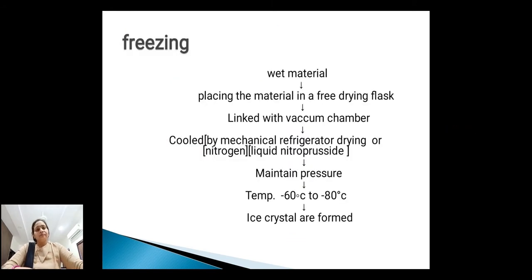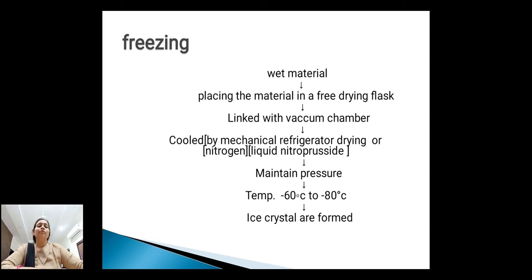Freezing. In this process, first we take wet materials and place the material in a freeze drying flask. After that it is linked with a vacuum chamber and cooled by a mechanical refrigerator or liquid nitrogen. At that time pressure and temperature are maintained at about minus 60 to minus 80 degrees centigrade. At the end of this freezing process, ice crystals are formed.